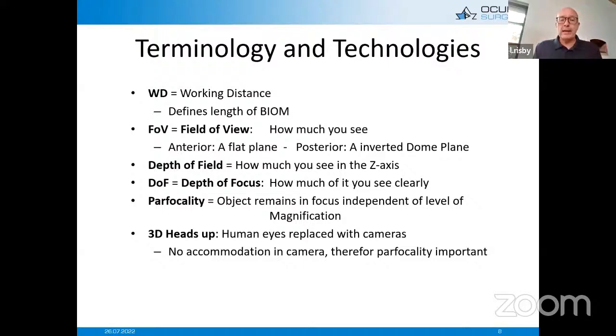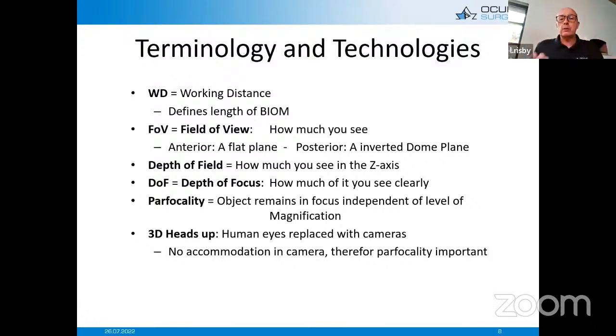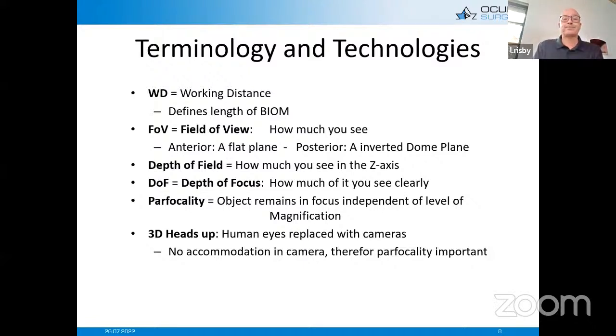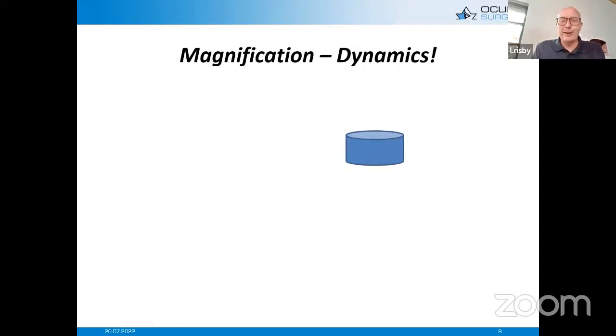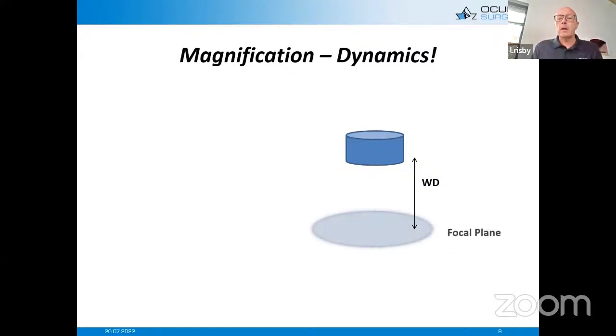Today we also use 3D heads-up systems where the human eyes are replaced with a camera. It has benefits but also drawbacks — there is no accommodation in the camera, and therefore focusing the microscope and the BIOM is even more important. So, what does this mean — the magnification dynamics? Every microscope, depending on the objective lens, has a working distance which defines the focal plane or focal point of the microscope.